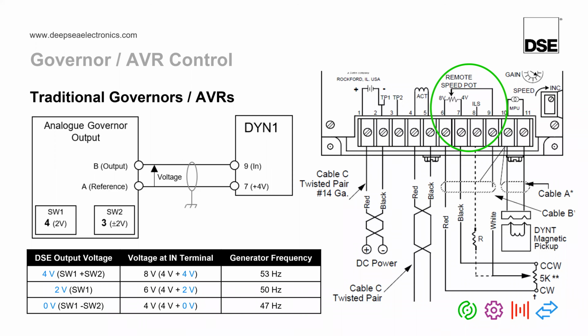Well, it seems there might be a couple of things in that question, so I'll try to answer them as best I can. Firstly, frequency is down to the engine governor, not the AVR. So if your engine is running at 53 Hertz, the first thing you should do whenever setting up a generator, without the DeepSea module connected in any way, shape or form, is make sure that the generator runs at 50 Hertz, if that's your nominal frequency, and then adjust the AVR to whatever the nominal voltage should be. So again, just to make it clear, frequency is controlled by the governor, not the AVR.